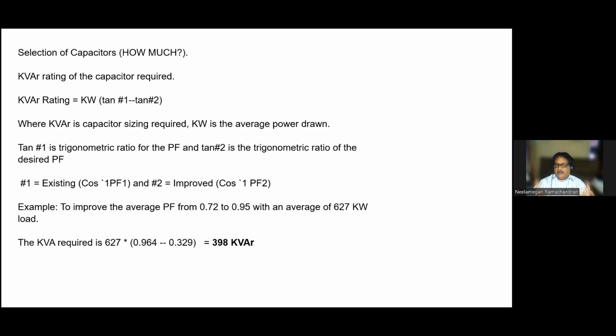So this is a simple calculation. See what power factor we are at now, and what power factor we are able to raise it to. If it is 0.72 and 0.95, it's cos inverse of 0.72 and 0.95. Using this formula, we can get the kVAR which we need. Having arrived at this kVAR, we have to diligently work out whether to connect it individually, in a group, or in the main panel. By distributing this, we can achieve 0.96, 0.97 without any problem. And maintenance of the capacitor also has to be taken care of.